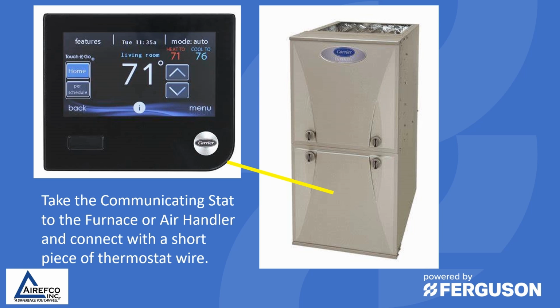If it still doesn't find the furnace or the fan coil with this short piece of wire, then there's either something wrong with the software, the user interface, or the furnace or fan coil control board.